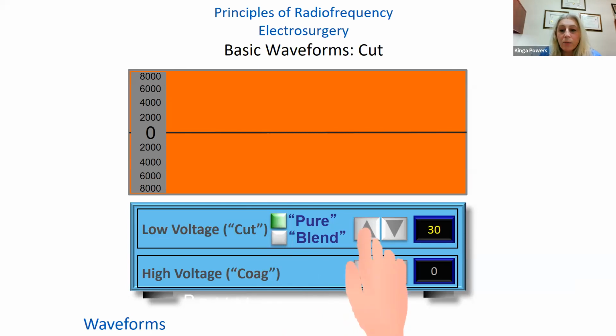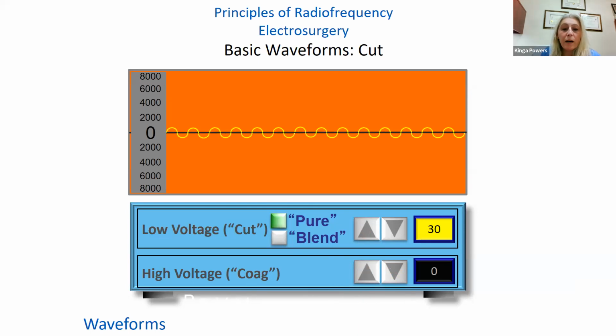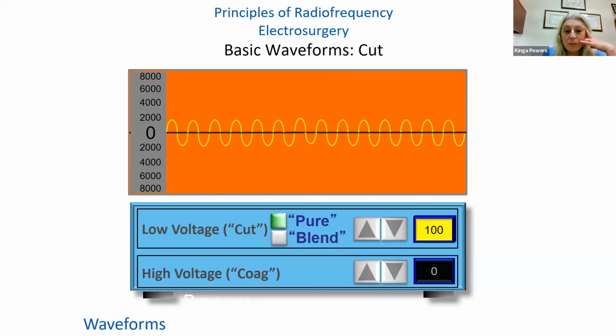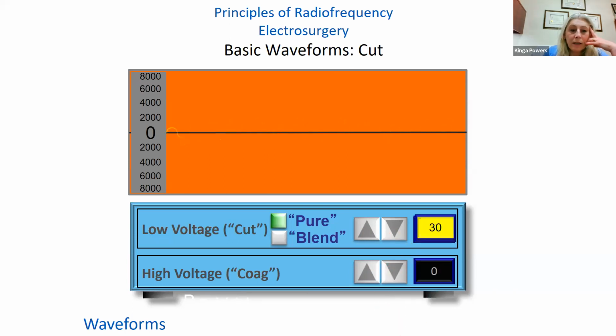If we look at our oscilloscope, what's important here is that it's a continuous sine wave, because the current is emitted 100% of the time, and it's an alternating current. You can see the sine wave, and it's 30 joules per second spread out through time. So it's a thin amplitude. You see the wave is very low amplitude, so the voltage is low. So cut is a relatively low voltage, continuous output waveform. But let's say we turn it up higher to 100, you can see that the voltage, or the amplitude, goes higher. It's still a 100% duty cycle. It comes out continuously without any breaks, but at a higher voltage, a higher amount of energy. And if you go back to 30, then it goes back to that lower voltage.